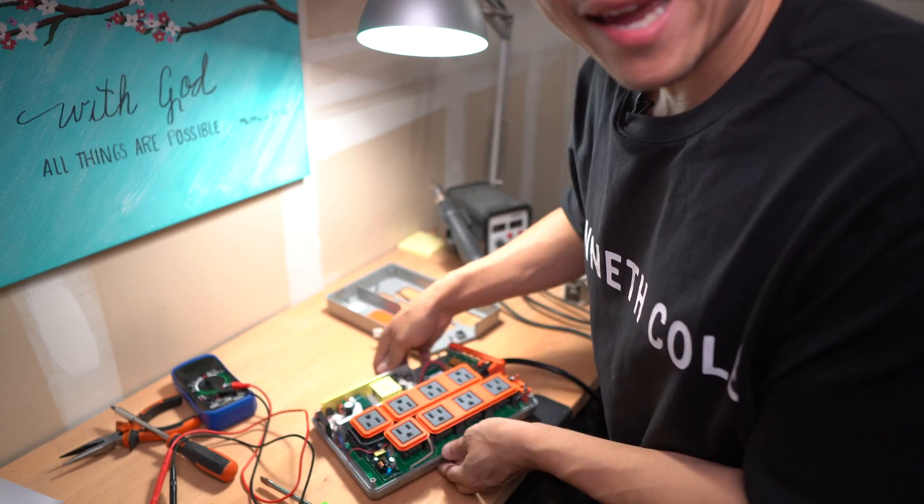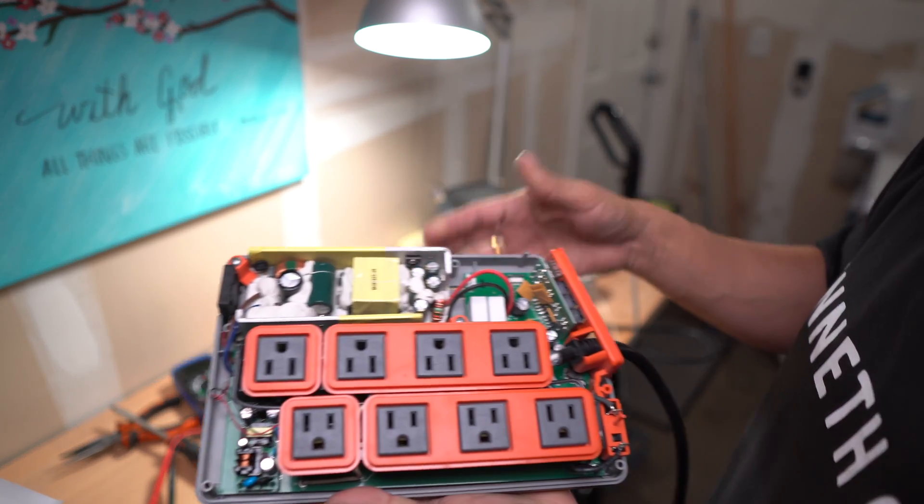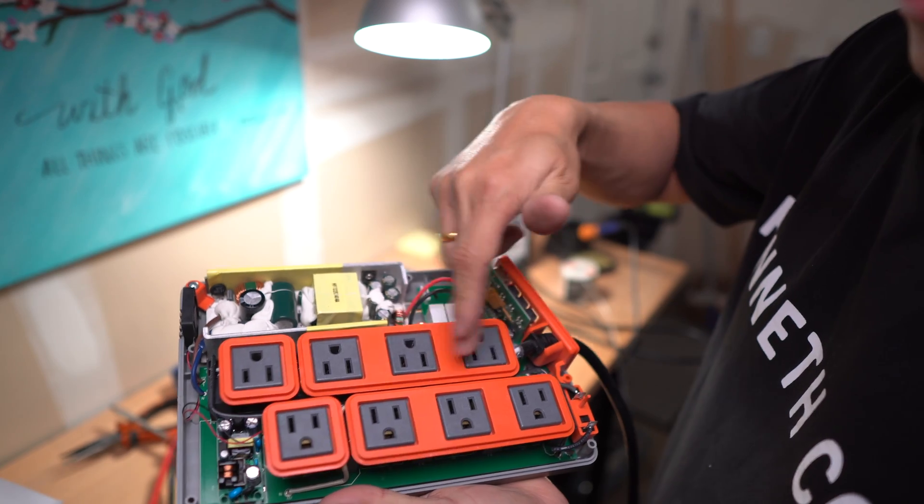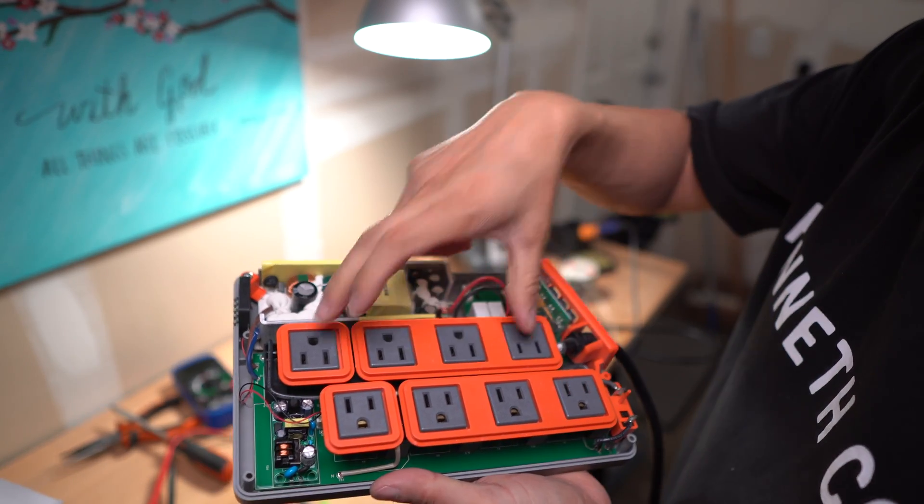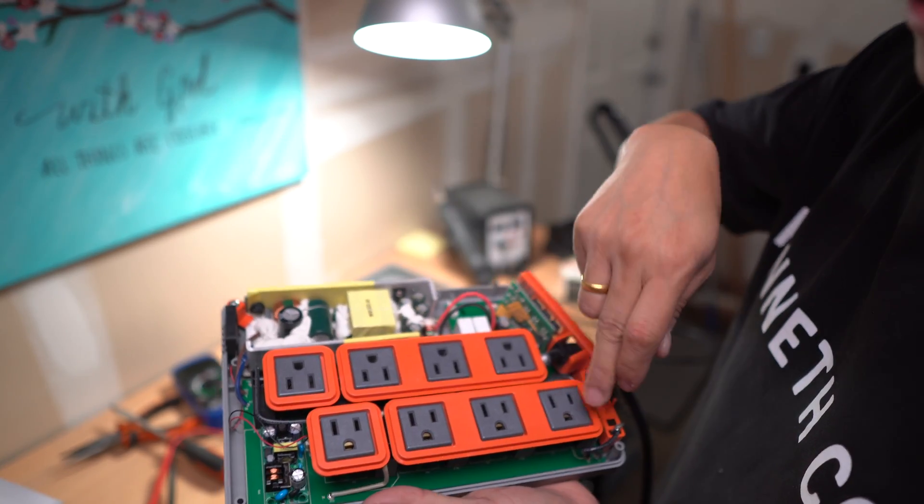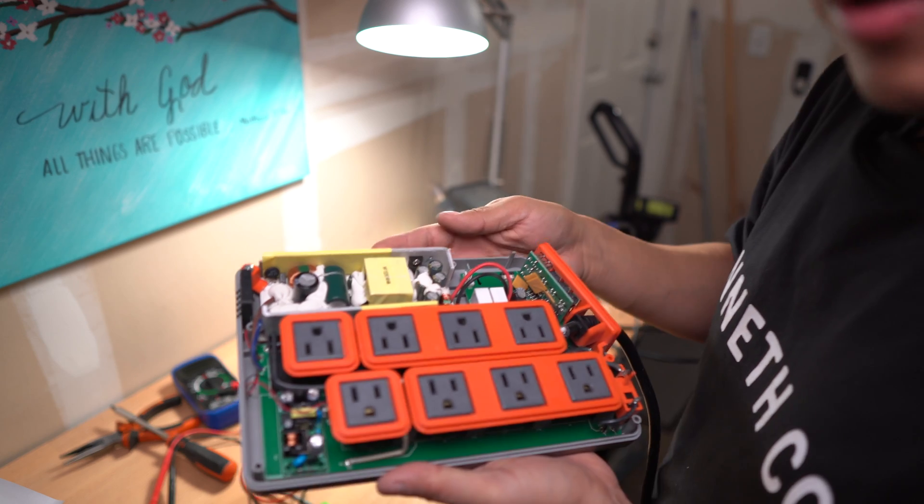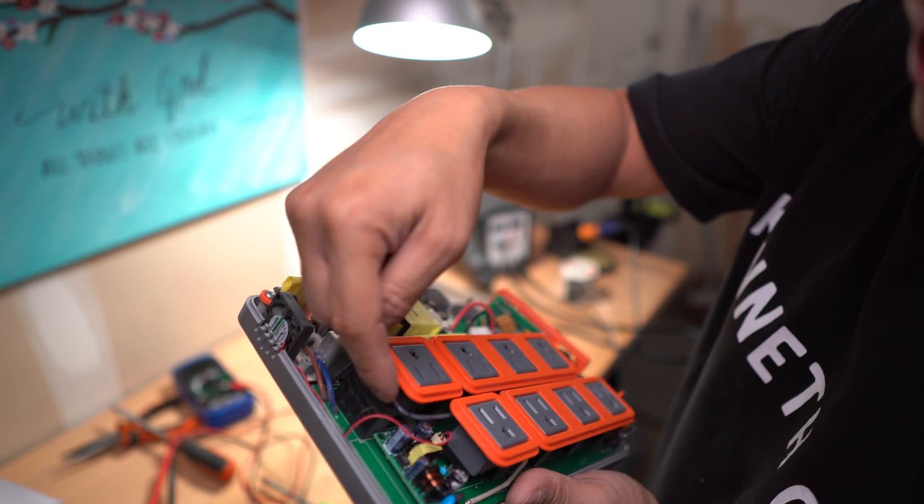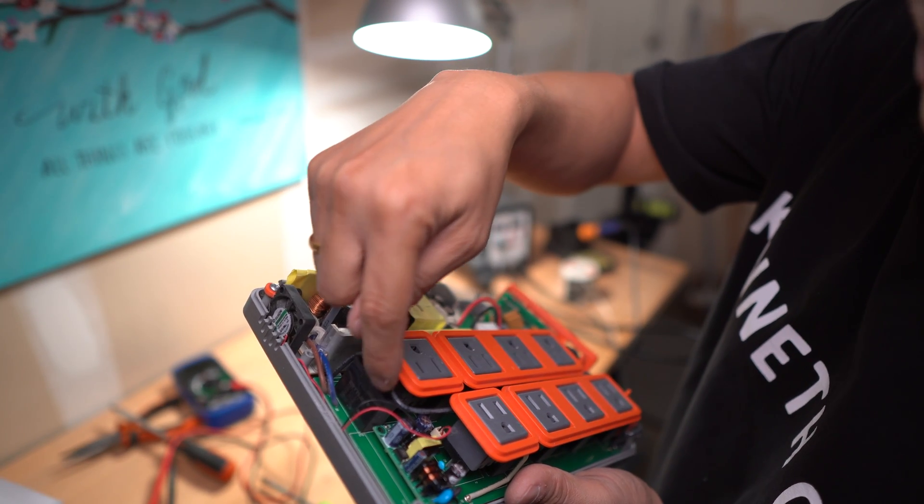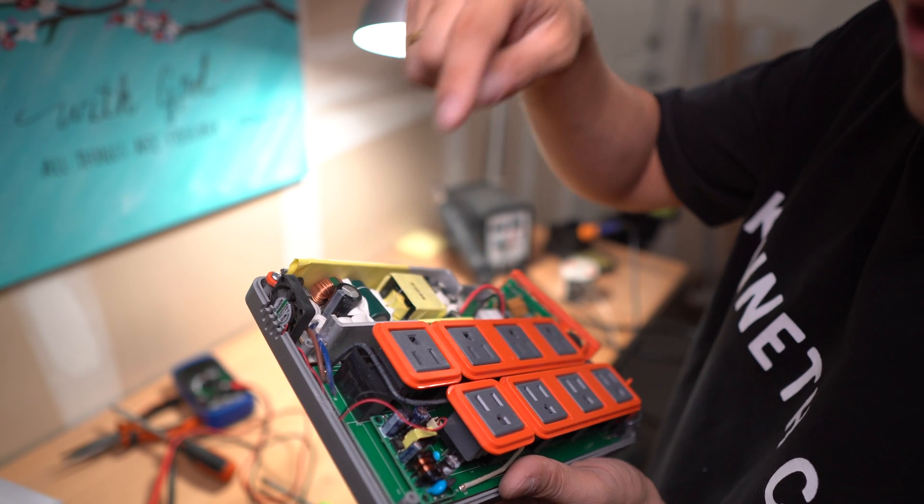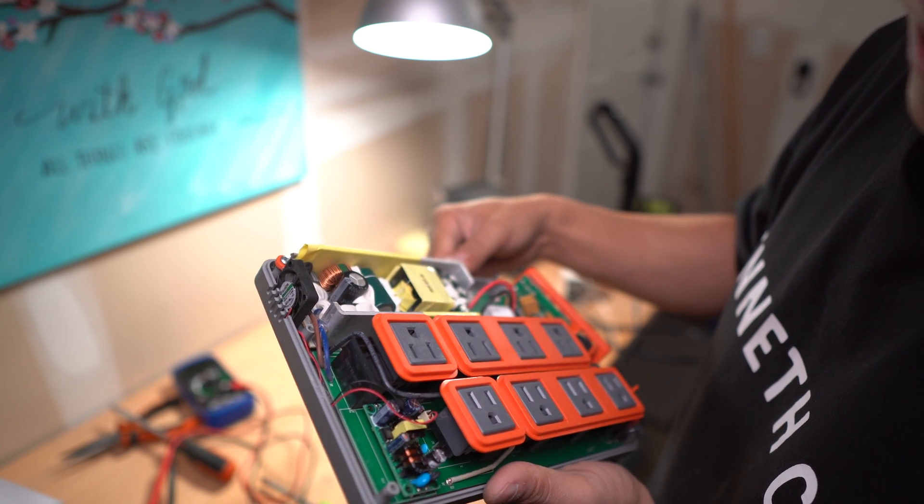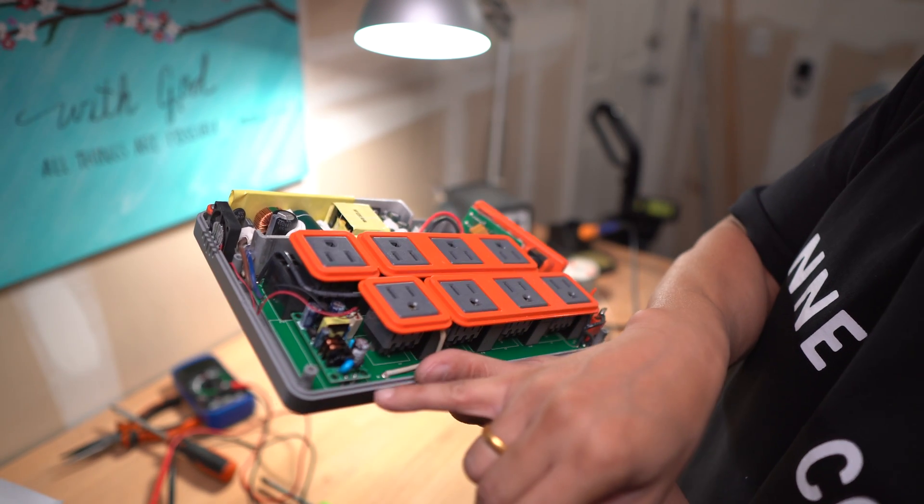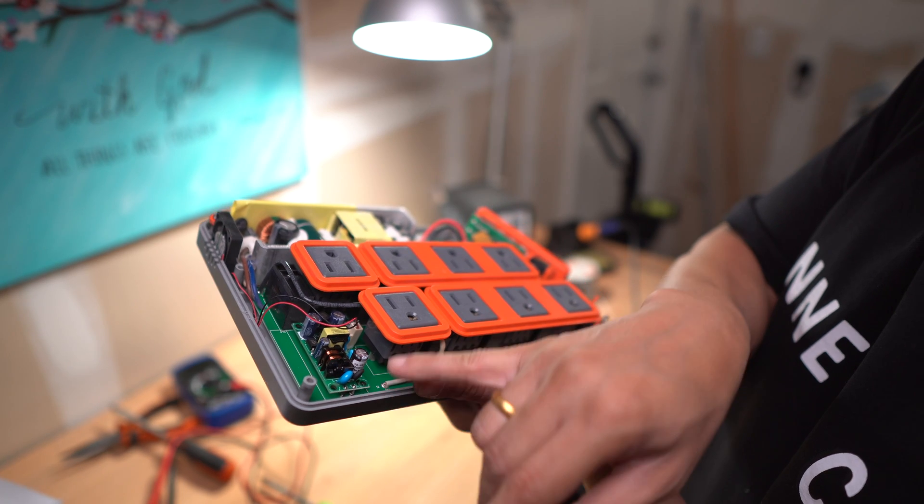I'm pretty confident that when I install this back into the cabinet everything's going to work the way it's supposed to work. Recap: what was happening was my outlets stopped working and I had measured the output and I wasn't getting any voltages. I took this unit apart and noticed the light wasn't turned on. I measured the two ends there, I wasn't getting the output that I was looking for. I measured these two in, I was getting the 120 volts in.